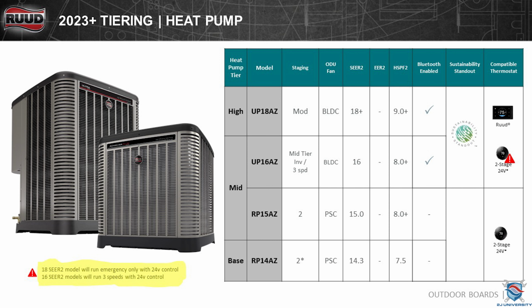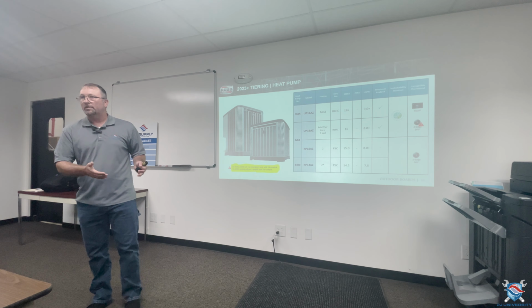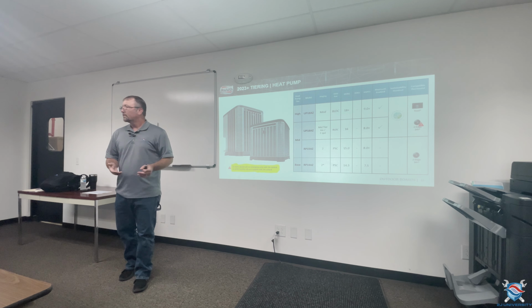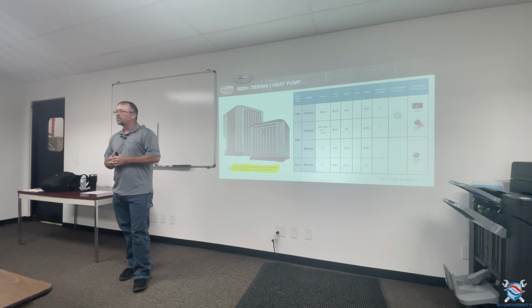Heat pumps, your base RP14, we have a mid-tier 15. These units are going to be 2-stage. Okay? So if for some reason you want to make it single stage, jumper Y1 and Y2, and it'll run in high stage all the time. I ran into a situation not too long ago where I had a guy call me and he's like, hey, I only have a single stage thermostat, what do I do? I'm like, well, you can either change the thermostat to a 2-stage thermostat, or you can jumper Y1 and Y2 and make it a single stage unit.